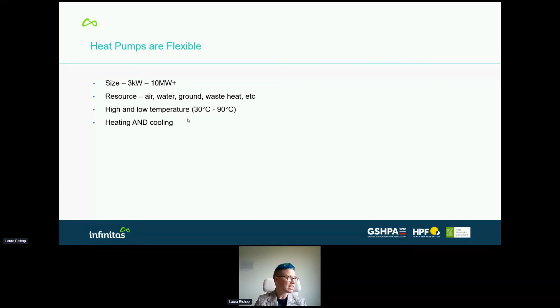You can get high and low temperature heat pumps. Traditionally, heat pumps generate temperatures of around 50 degrees C, and they work more efficiently the lower you go. But you can now buy propane heat pumps, ammonia heat pumps that will do 80, 90, 95 degrees C flow temperatures. They can obviously do heating and cooling because they are essentially chillers working in reverse. You can have the same machine producing heating and cooling, so no longer any need to have a chiller on the roof and a gas boiler in the basement.